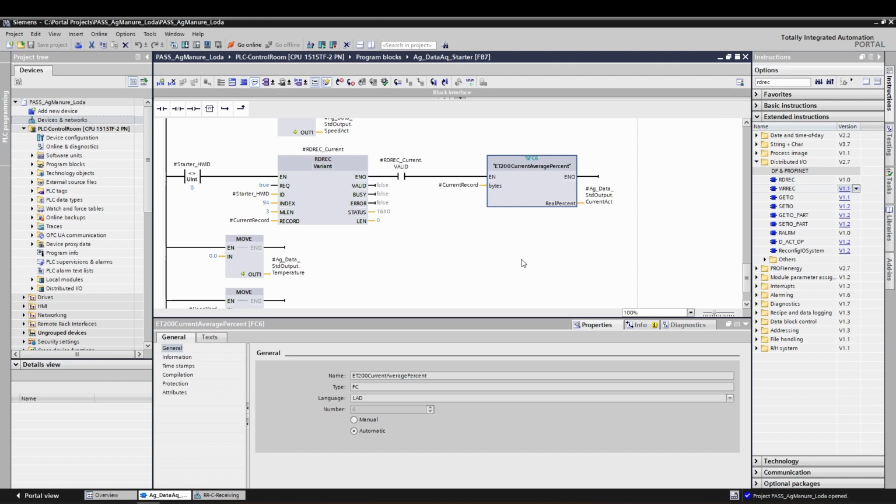Now that you understand how to read data records from an I/O device, this opens up a whole new world. Once you have your device into your hardware config, it gets immediately assigned a hardware ID, and all you need is that hardware ID and your manual telling you the data records in order to access those data.